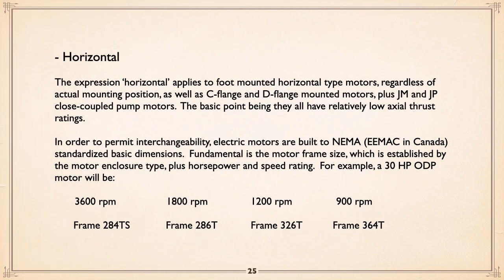Now, talking horizontal motors. The expression horizontal applies to a foot-mounted horizontal type motor, regardless of the mounting position. In other words, it may be intended for being mounted horizontally, but if it's mounted vertically, it's still considered a horizontal motor. Sounds slightly crazy. And you can get different flanges on the end of the motor so that it can be mounted vertically or horizontally to a piece of equipment. And there's JM and JP. What those are, basically, is like a close coupled centrifugal pump. We talked about that, and the shafts are set up so you can have either mechanical seal or packing. The mechanical seal shaft is quite a bit shorter because mechanical seals are fairly compact, which means less deflection because of the radial thrust of the pump. JPs are much longer because packing is much longer, but you can get motors with those shafts on.